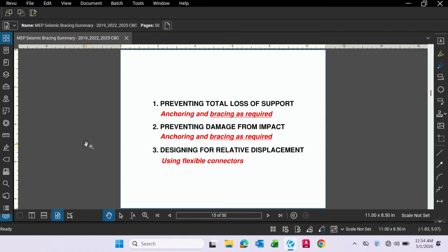Preventing damage from impact, again, you want everything anchored down so that they don't move. You add bracing so that they don't collide with each other. Design for relative displacement, the easiest way to handle that is to provide flexible connections between two components so you can allow for that flexibility and reduce the stress on the connection points.